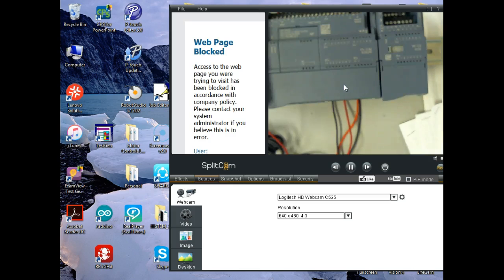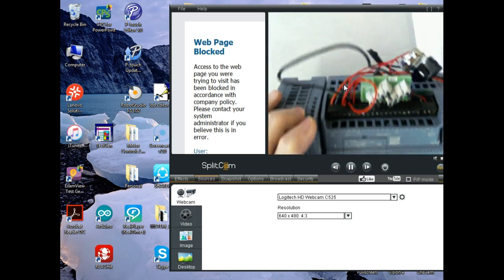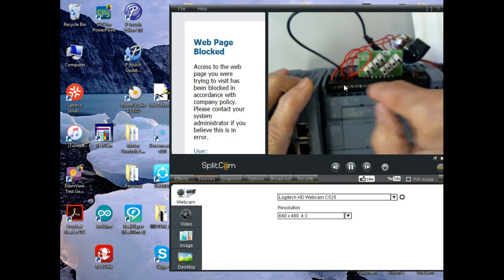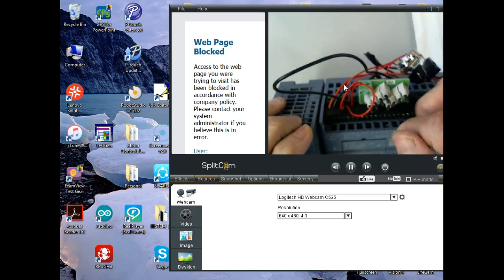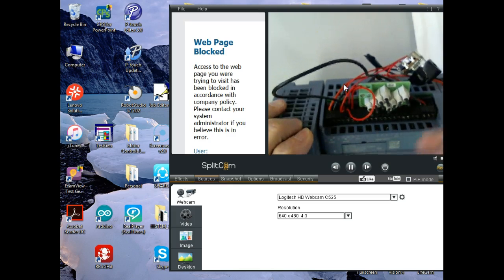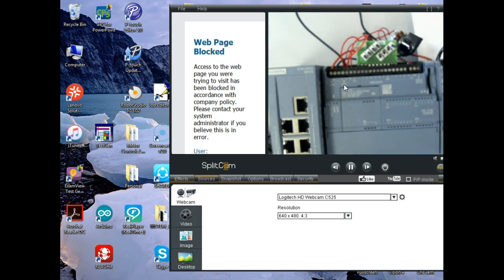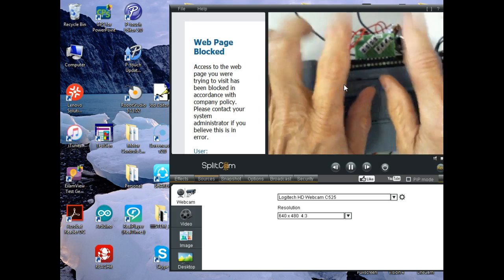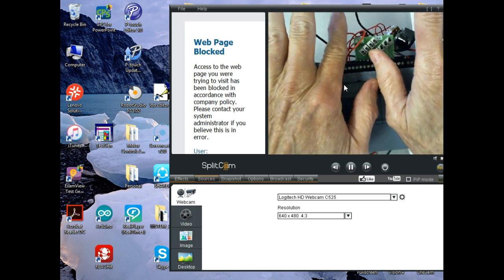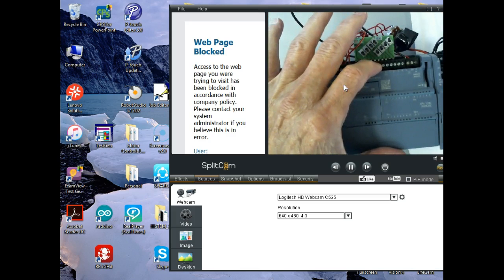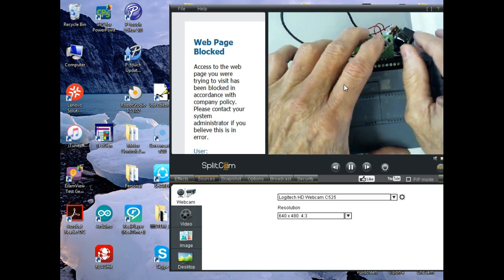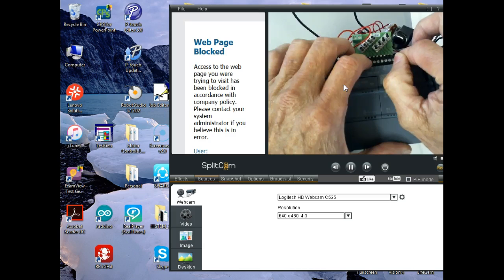That's pretty neat. This guy here has a unique feature too, where the actual where we wire the inputs and outputs, you can get a screwdriver and snap this thing off. So what's nice about this is if you look at the 1100s that we have and the 1200s, if I had to replace the PLC, what would I have to do? I'd have to rewire that whole thing. On this one, if I had to replace the PLC, I could snap the terminal boards off, bring my new PLC in there with the programs in it, snap it in there, and snap these things in, I'd be ready to go. This is becoming very, very popular now.